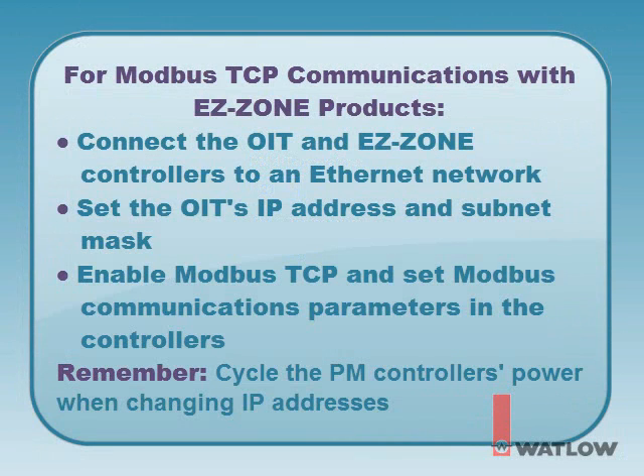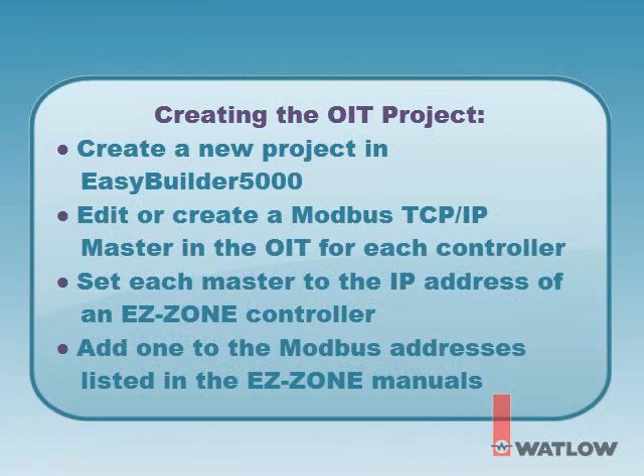To review: to set up Modbus TCP communications between a Silver Series OIT and EZZONE products, you must connect the OIT and EZZONE controllers to an Ethernet network, set the IP address and subnet mask in the OIT, enable Modbus TCP and set the controller's Modbus communications parameters including the IP address, subnet mask, display units, and non-volatile save preference. These can be done in any order, but all three must be done — and don't forget to cycle the power to the controllers if you change the IP addresses. The steps for creating a new Silver Series project that communicates with EZZONE products via Modbus TCP are: create a new project in EasyBuilder5000, edit or create a Modbus TCP IP master in the OIT for each EZZONE controller, set each master to the IP address of the corresponding EZZONE controller, and remember when addressing data in EZZONE devices to add one to the Modbus addresses found in the EZZONE users manual.